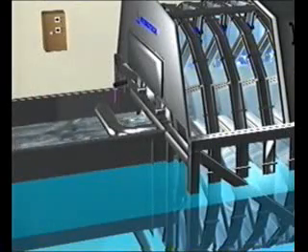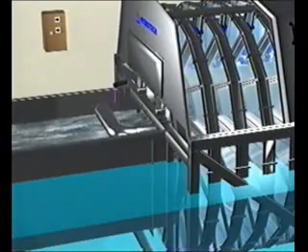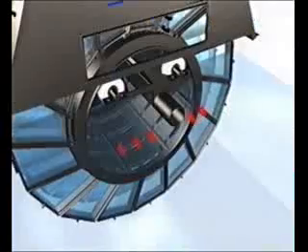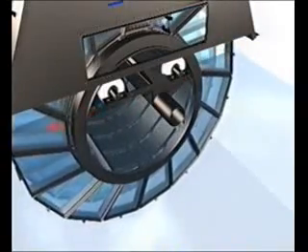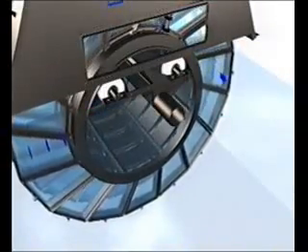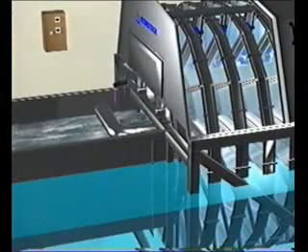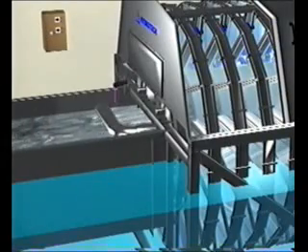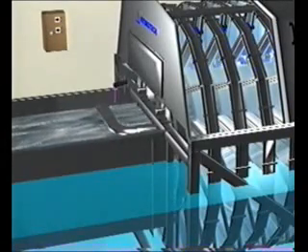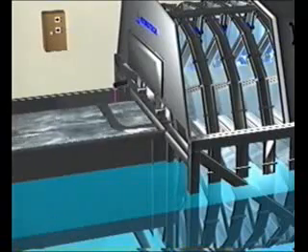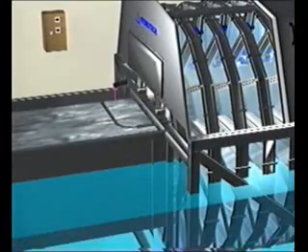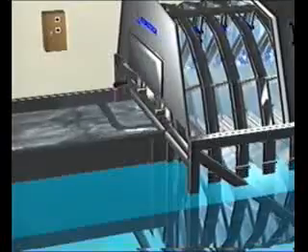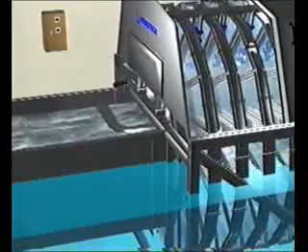The principle behind a disc filter and a drum filter system is the same. The water flows into the drum by means of gravity and is subsequently filtered through the filter panels. The separated particles which collect on the inside of the filter cloth eventually create an increase in pressure, causing the water level in front of the filter to rise. When the level of water reaches an inbuilt sensor in the system, the rotation and backwash cycle is started by means of the automatic equipment.